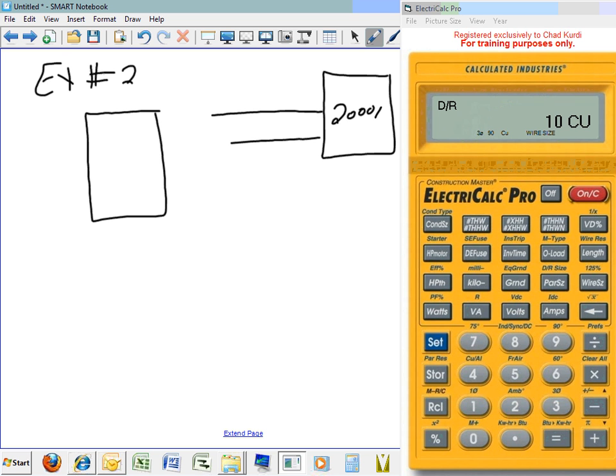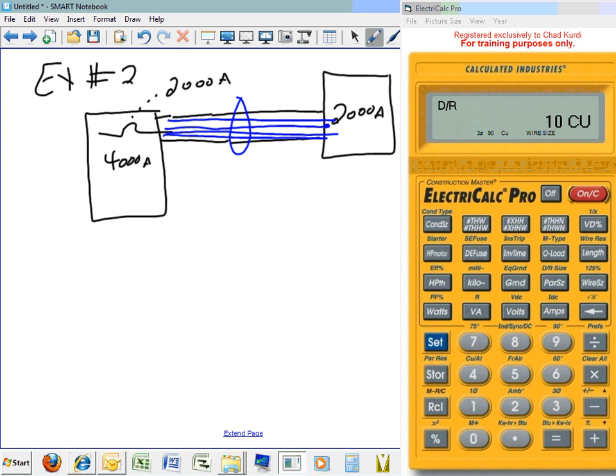This is 2000 amps, and this is 4000 amps. My circuit breaker here, what do you guys think the circuit breaker would be? 2000 amps. So I have a 2000 amp feeder feeding a 2000 amp panel. So I need to pull all the conductors going from here to feed that panel: hot, neutral, and ground. Long story short, find me a conductor that can carry 2000 amps. You can't. So let's go parallel. So sizing, find 2000 amp feeder conductors.